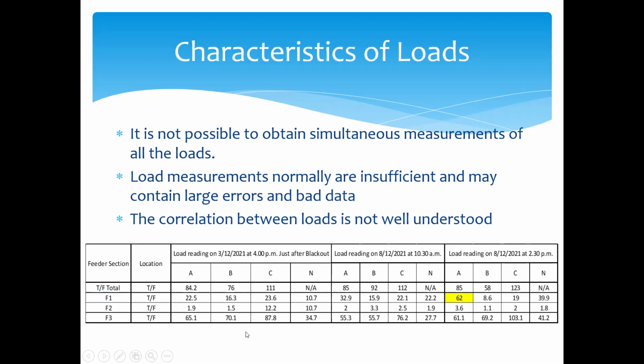So if you consider these values, I got the transformer total from the meter, and subsequently we get the values in the feeders within a few minutes. So you can see that these current values are taken within a few minutes, so they are not simultaneous measurements. Because of that, they may have errors and even bad data. We don't even know whether they are bad data or not, because it's not easy to predict.